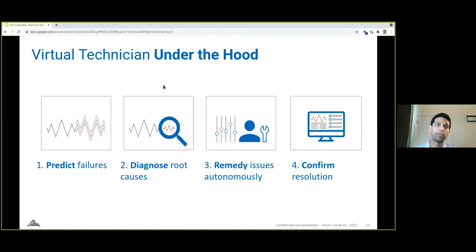The second thing would be diagnosing the root causes. So there's a combination of machine learning and decision trees that go into diagnosing why this is actually happening, rather than just identifying symptoms, which would be a case getting warm or something to that effect, or maybe a compressor shutting off or a condenser fan stopping, not running. For a lot of these situations that we encounter, we can remedy those issues autonomously, so changing that set point back to what it should have been.